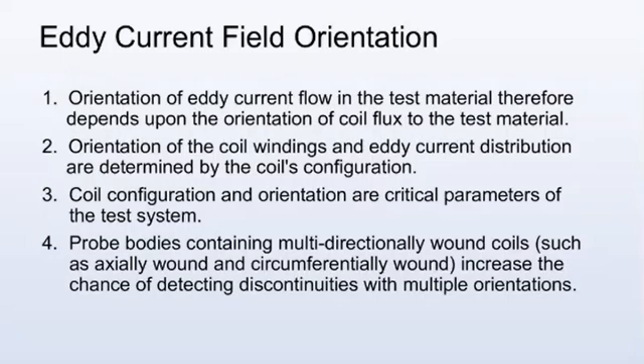Probe bodies containing multi-directionally wound coils, such as axially wound and circumferentially wound, increase the chance of detecting discontinuities with multiple orientations.